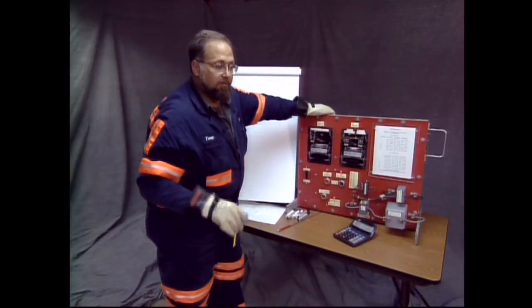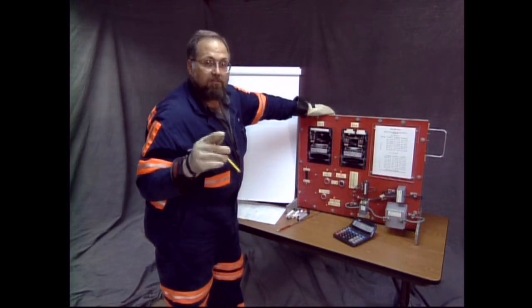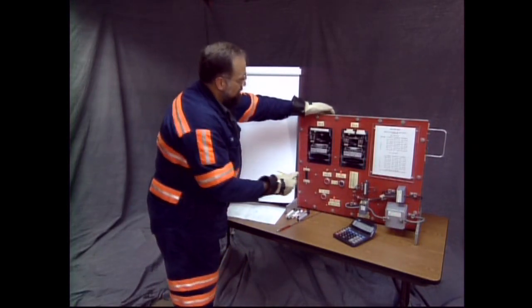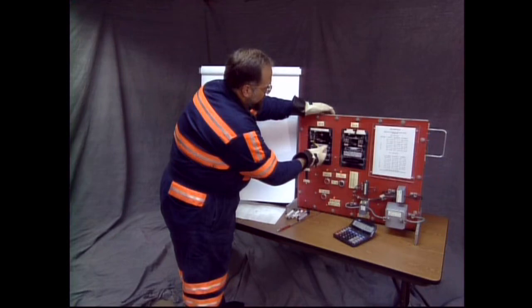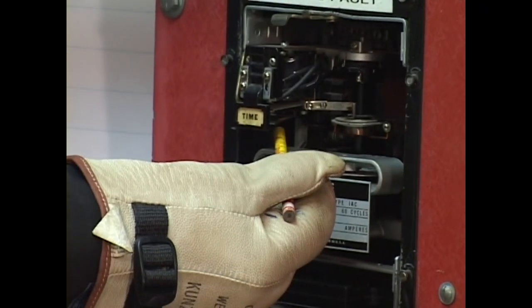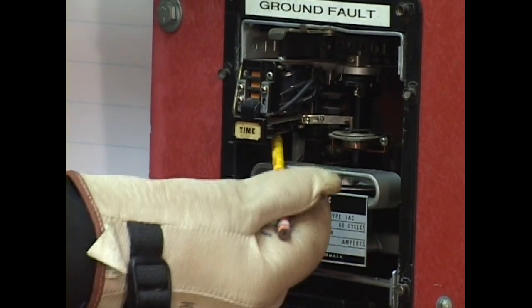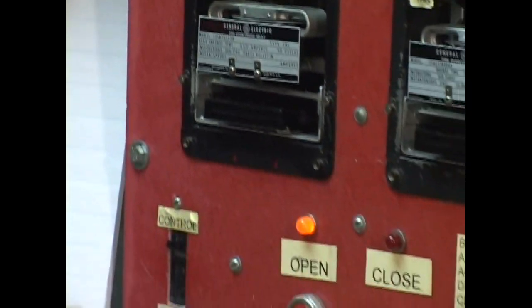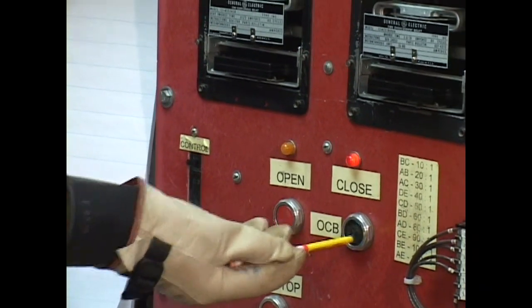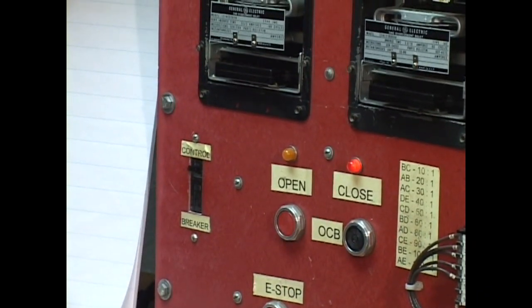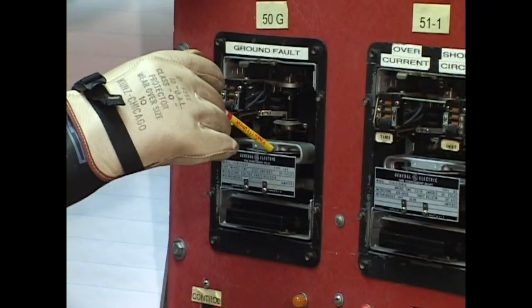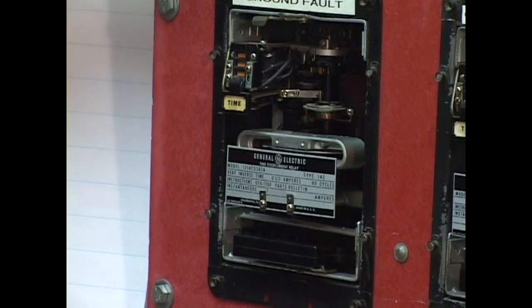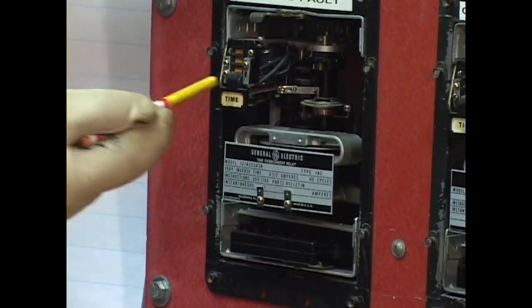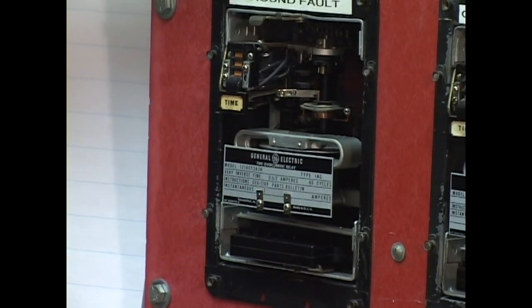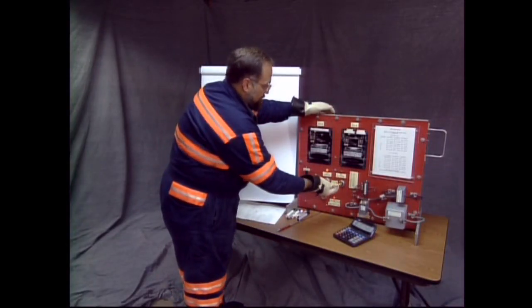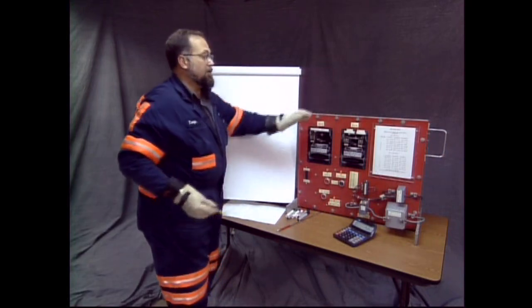That's one auxiliary. For our manual operation of our second auxiliary, I'm going to manually operate the ground fault relay. You raise contacts gently, and you saw the breaker open, OCB opened. I'm going to reclose it. I'm going to manually operate my ground fault time disc. Gently turn the wheel around, make this post come in contact with that point. It opens the breaker. Okay, now you reclose the breaker.